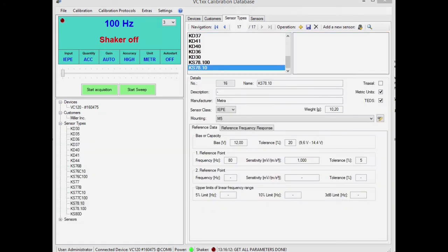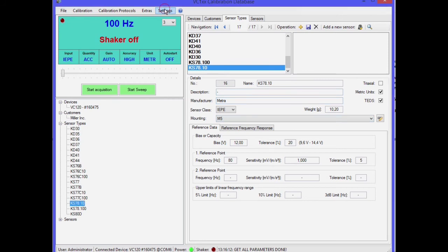Under Customers, you can enter the contact details of the client commissioning the calibration. Sensor types is used for entering and selecting typical parameters of the sensor to be calibrated. Here you can specify the type description, the manufacturer, sensor output type, weight, mounting method, the unit of measurement to be used, transducer electronic datasheet, and so on. You can also enter one or two reference frequencies to which the sensors should be calibrated. Entering the permissible tolerance will enable you to check the plausibility.